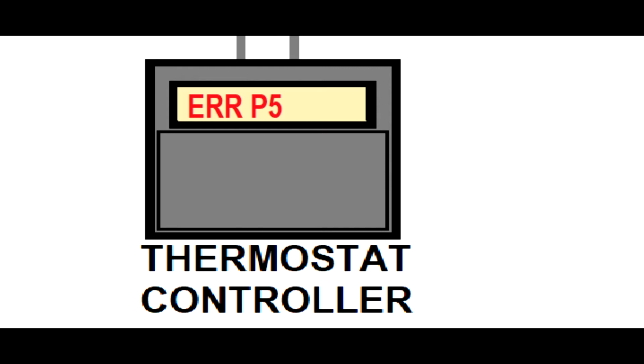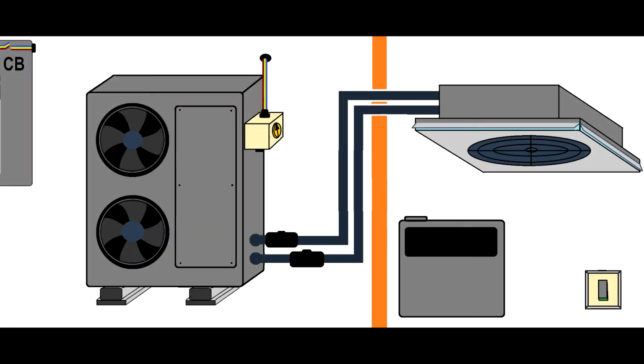Dear friends, I would like to talk today about Mitsubishi cassettes, especially this fault code P5, which refers to a condensate water issue. It could be the pump, it could be a blockage onto this drip tray, and this is the cassette.